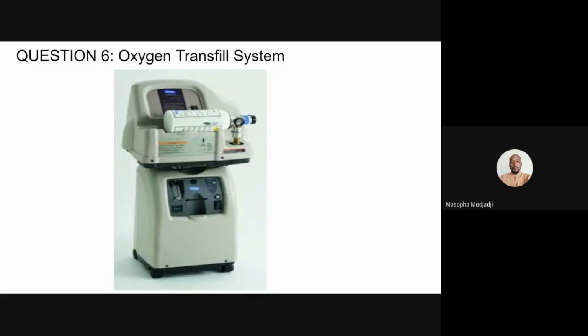Place an oxygen refill machine on top of an oxygen concentrator and connect them to each other. Plug them into an electrical socket and press the power button to turn on the machine, just like it's shown in the picture there. And then connect your oxygen tank and cylinder to the refill machine. Make sure that the oxygen conserver or regulator on the tank is turned off. If you are not using a conserver or regulator to fill the oxygen cylinder, verify that the cylinder valve is closed to ensure proper filling. Remove any protective caps from the oxygen tank. When not in use, replace the protective caps to prevent dust buildup.